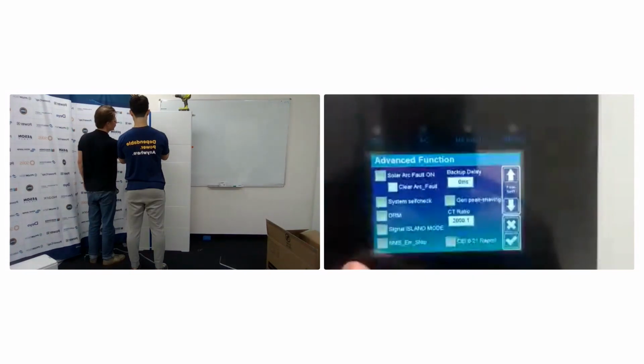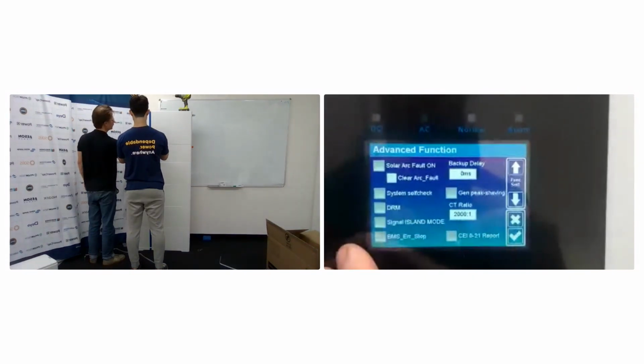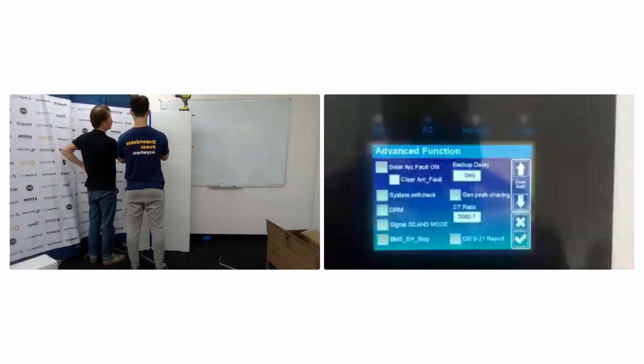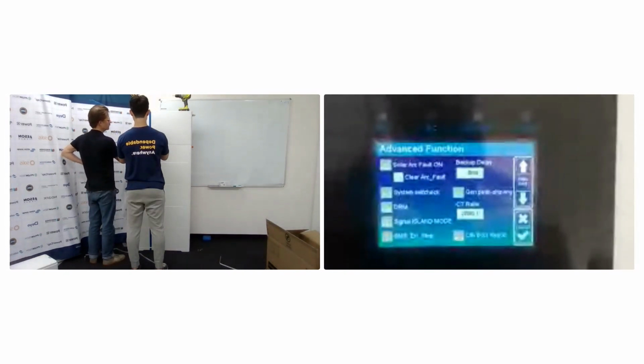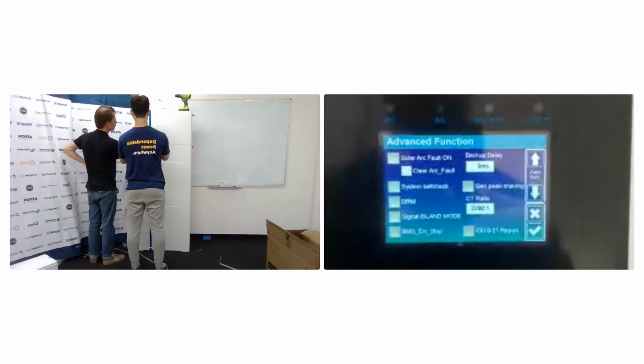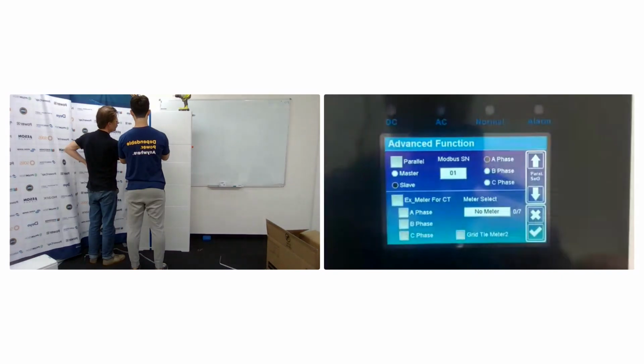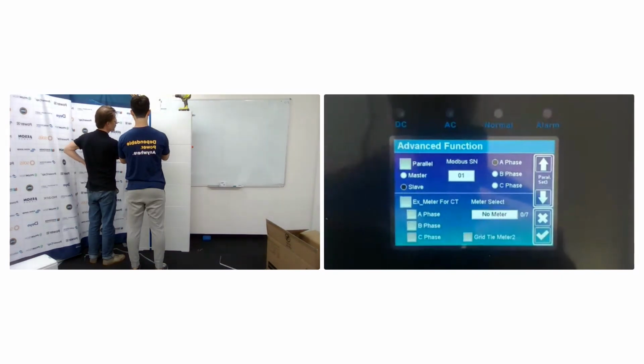That's interesting, this comes not ticked on for this, which is good. The other inverters come with DRM switched on as default, and you have to switch it off unless you're in Queensland. That's a really easy error to make. You want to have BMS error stop off. You wouldn't have to bother with this just for a single stack.